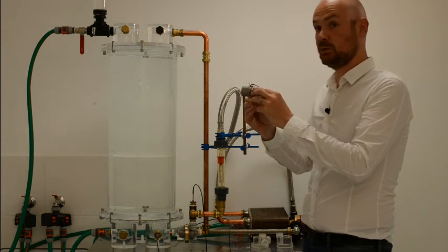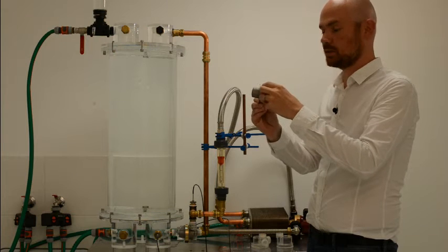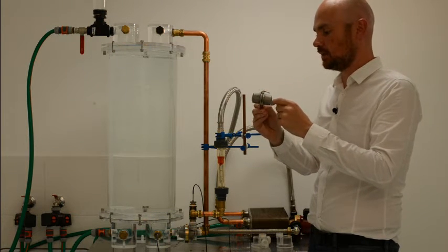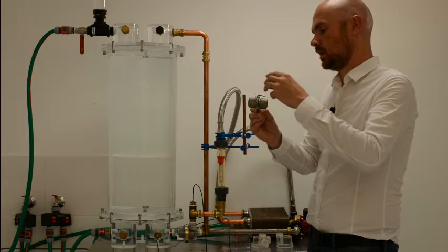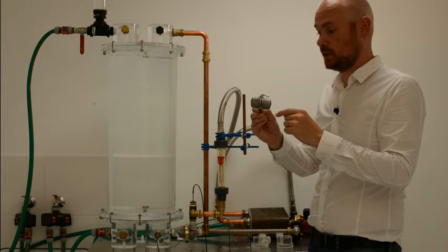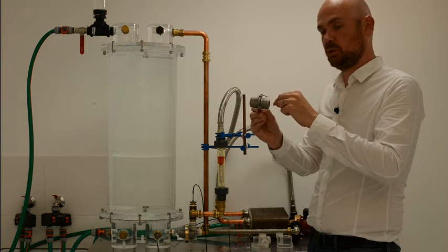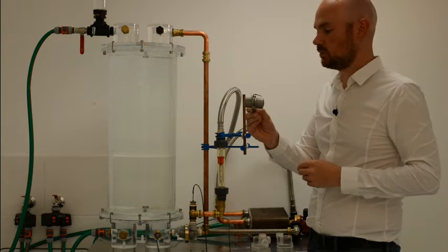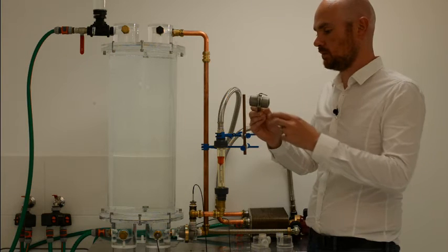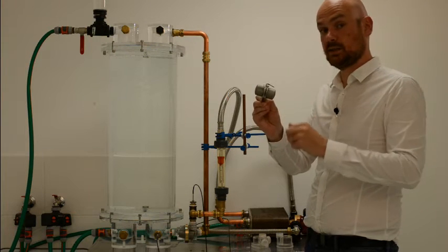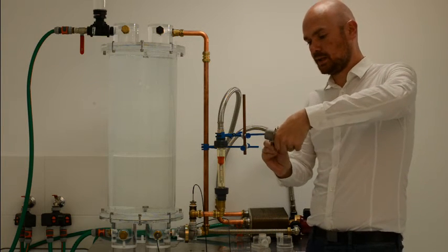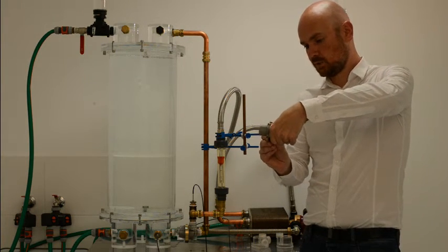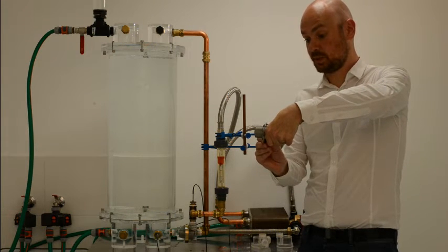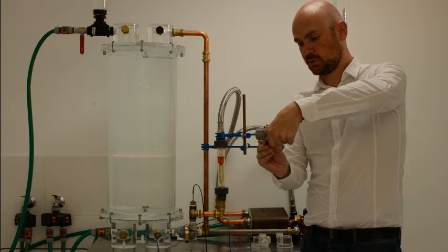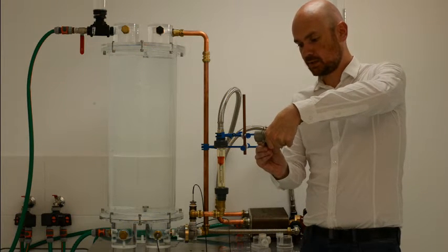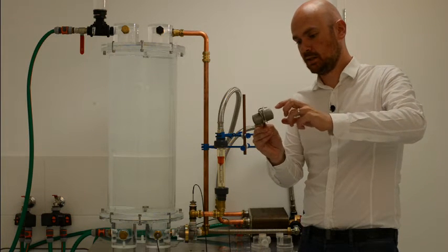So it consists of a float in the middle, which has a little dividing wall in the middle of the float inside, and the dividing wall has a hole in the bottom. So basically this actuator is filled with working liquid, and the working liquid will always want to move towards the colder side of the actuator, driven by the vapor pressure, which is always higher on the warmer side of the actuator. So at the moment all the liquid is on this side of the actuator, which is why it's tilting that way. But if I then heat up this side of the actuator with my hand, because my hand should be warmer than the ambient temperature, then all the liquid will start transferring to the other side of the actuator, and the actuator will start tilting in the other direction. As you see here, now it's tilting to the other direction.